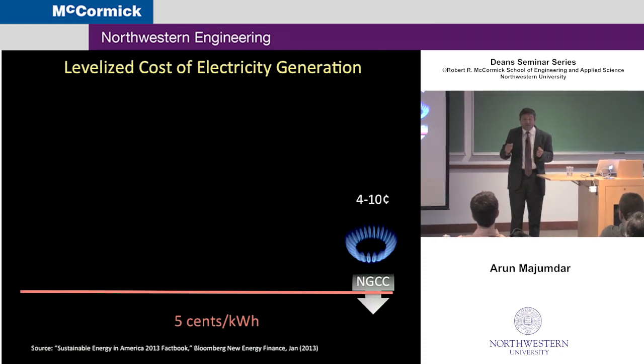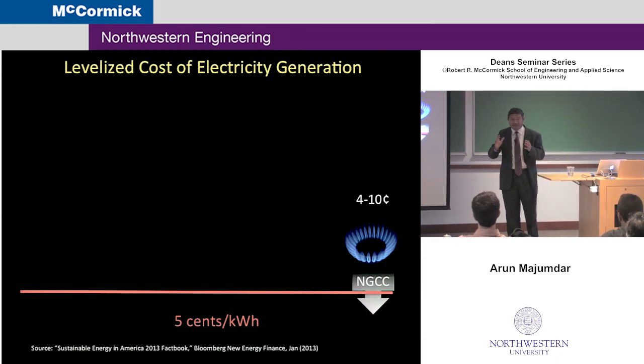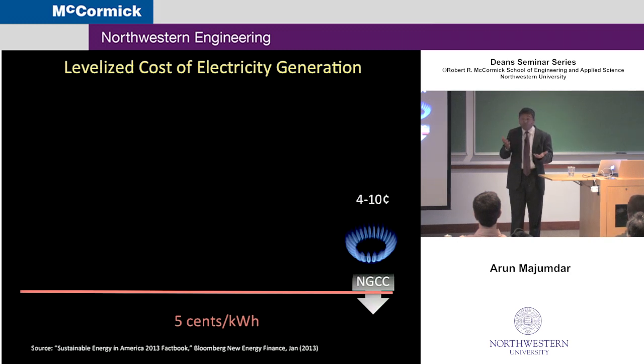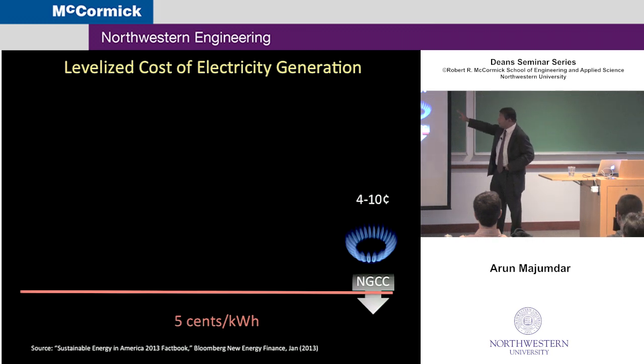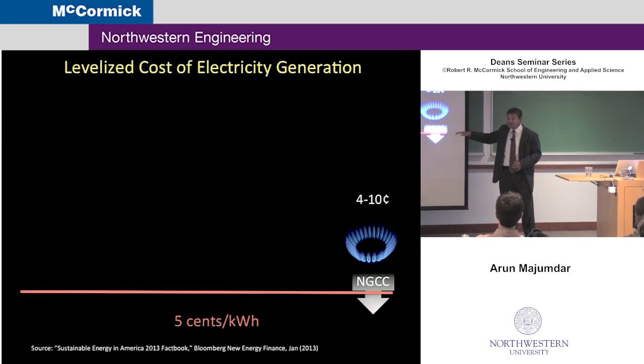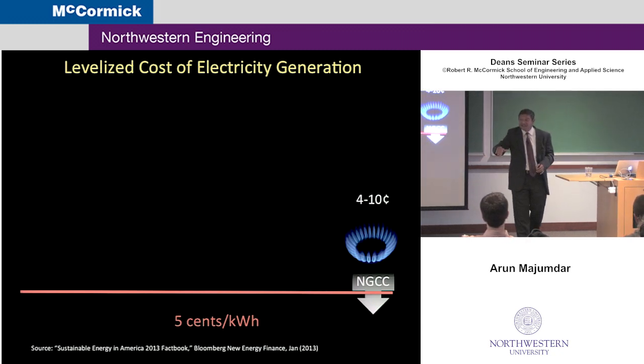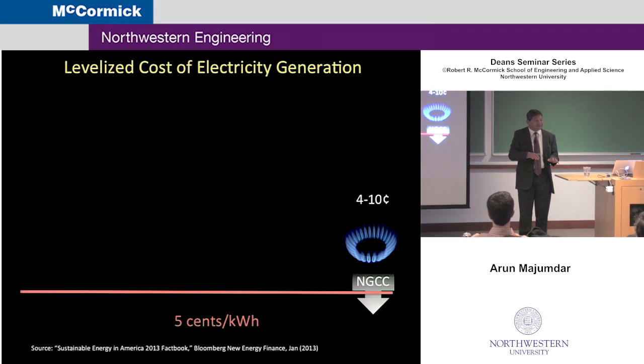And they ramp up at 50 megawatts a minute. They not only provide baseload power, they can ramp up and firm intermittent sources like wind. So these are natural gas combined cycle plants. The low cost of natural gas feedstock, as well as the highly efficient turbine, makes it the cheapest, and that sets the bar for every other electricity generation scheme.